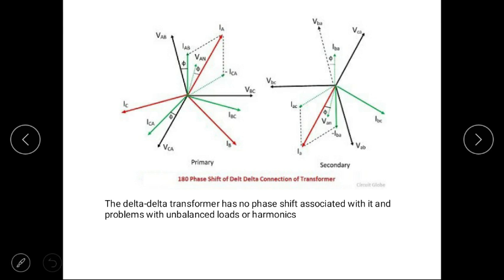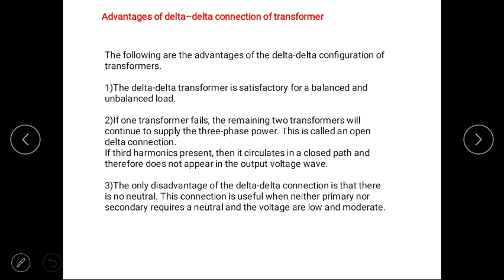The delta-delta transformer has no phase shift associated with it and no problem with unbalanced load or harmonics. Advantages of delta-delta connection: First, the delta-delta transformer is satisfactory for both balanced and unbalanced loads. Second, if one transformer fails, the remaining two transformers will continue to supply three-phase power — this is called an open delta connection. Third, if third harmonic is present, it circulates in a closed path and therefore does not appear in the output voltage waveform.